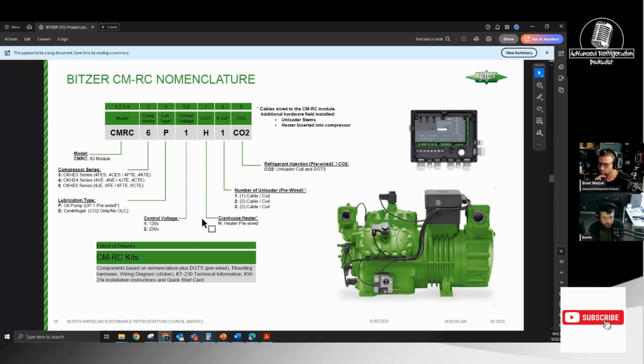So why didn't you order one for all the heads? Because this was done on a project just to make the cycling issue go away. Otherwise I would have had to replace the center head too, and I'm already waiting a month and a half to two months to get the Copeland heads. Since they're on back order for these compressors, we went with this. We were trying to get something as fast as possible to stop it from eating itself. It was cycling itself to death. Yeah, it was awful.